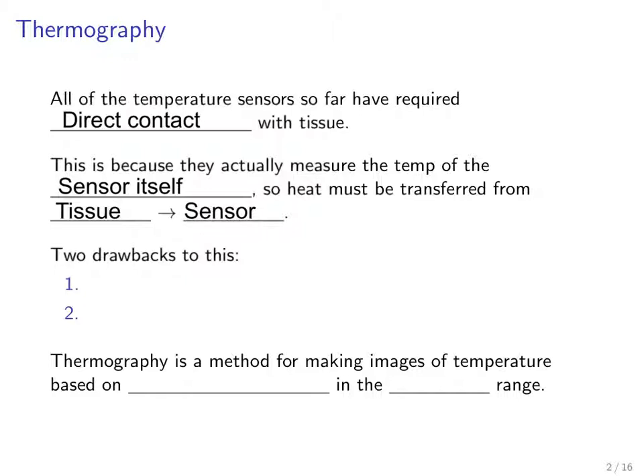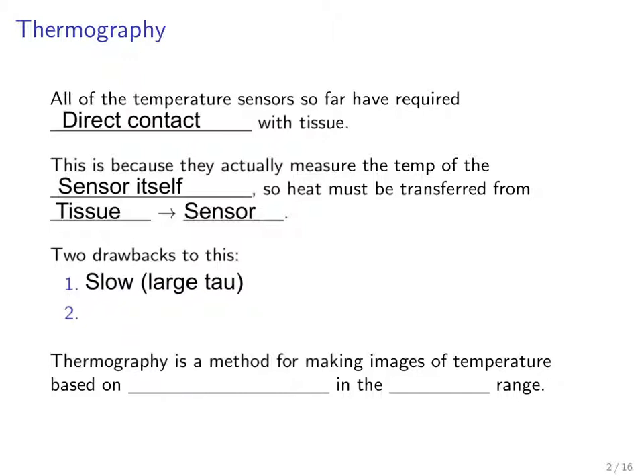Now there are two drawbacks to this. One is that it can be a slow process, embodied by the fact that we have a relatively large time constant tau with which the heat transfers from the tissue into the sensor. The other potential issue is that you have the potential for unsanitary conditions — it's potentially unsanitary to bring a sensor directly into contact with tissue, and also potentially invasive if you need a more internal measurement.